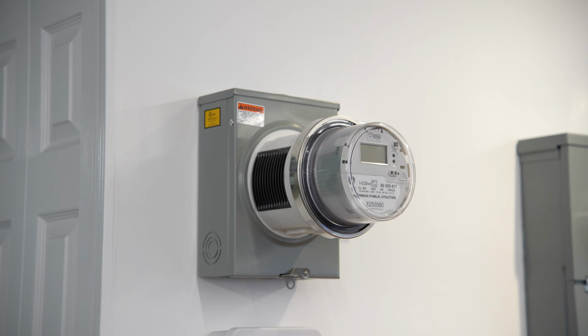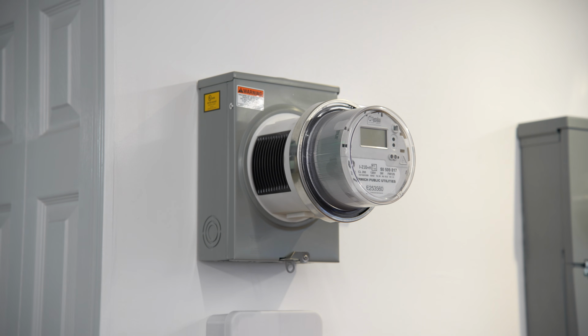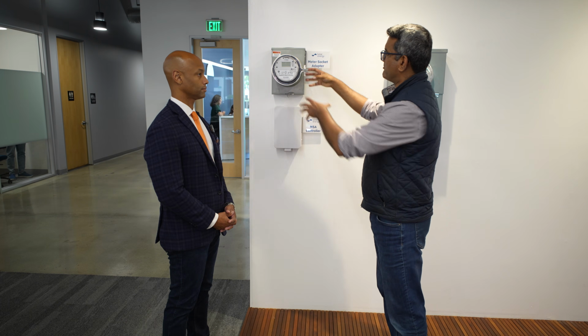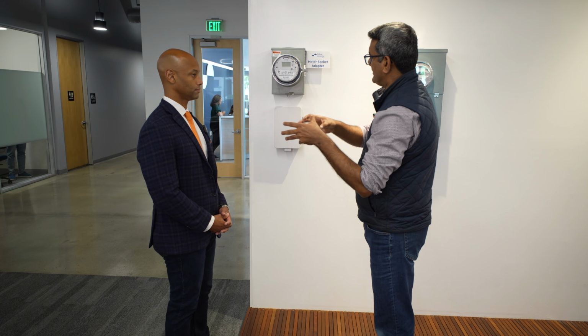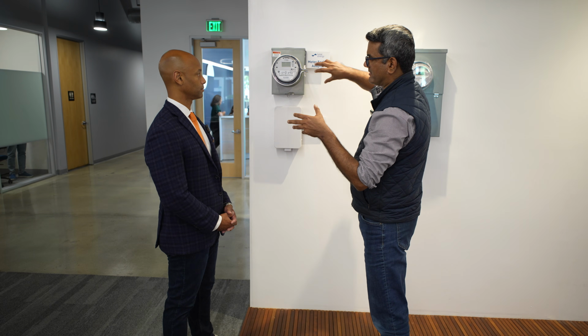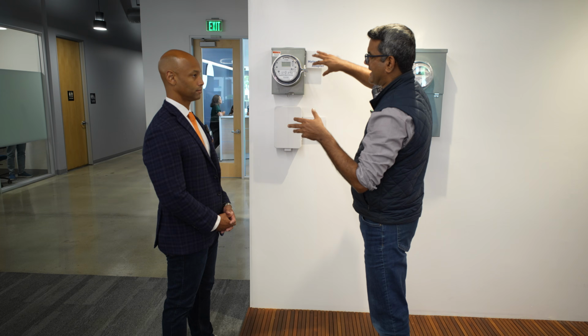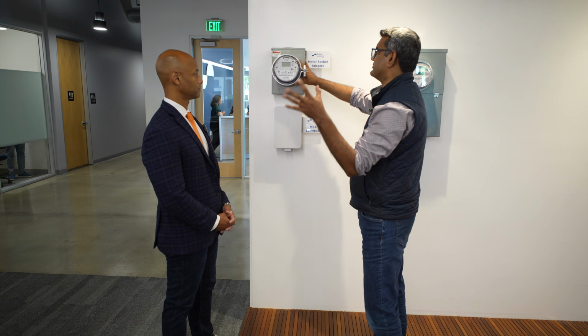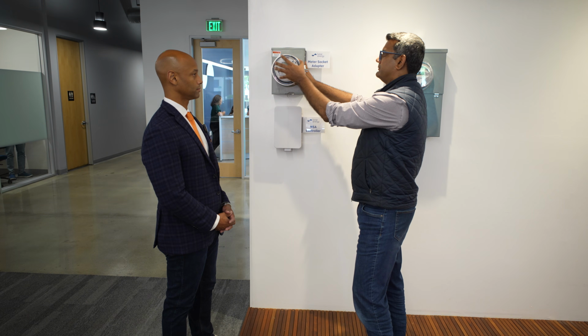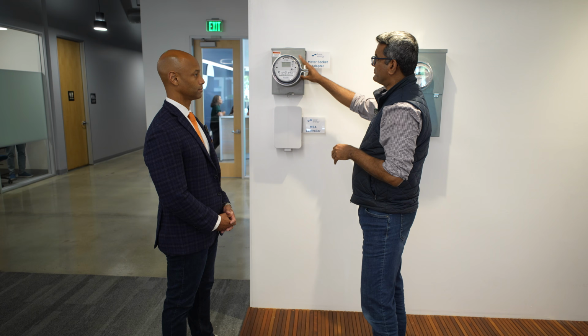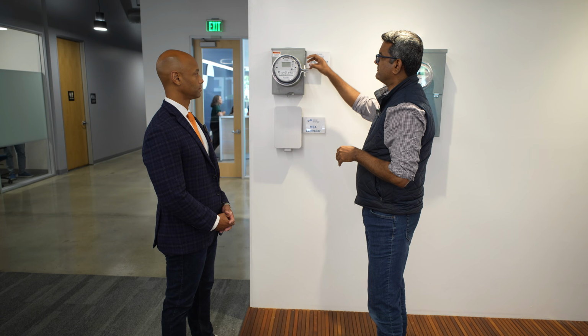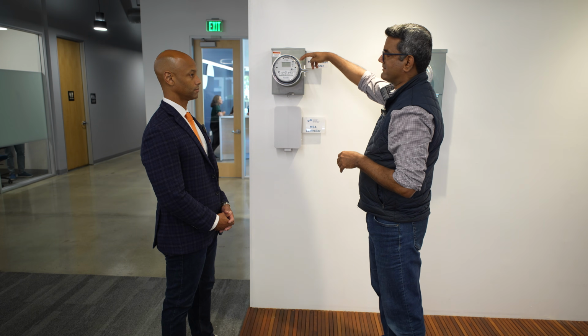That adapter has a relay similar to what the bridge has, and you remove the meter of the home. You snap in the adapter. It's a blade-type disconnect, so it's very easy to snap in, and then you snap in the meter on top of that. When you do that, you essentially make the disconnection point at the grid point.